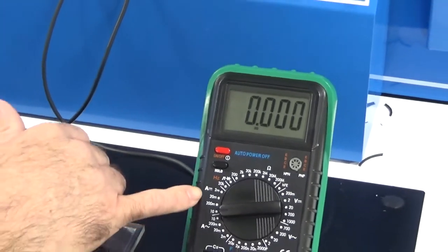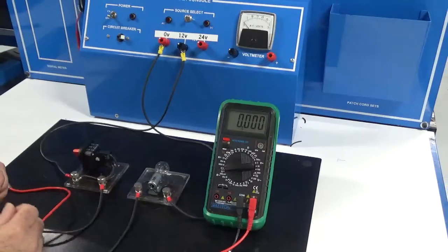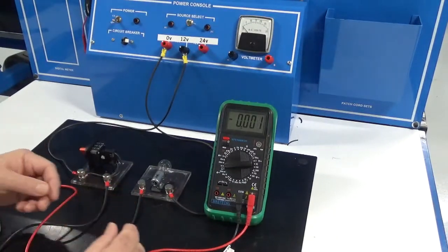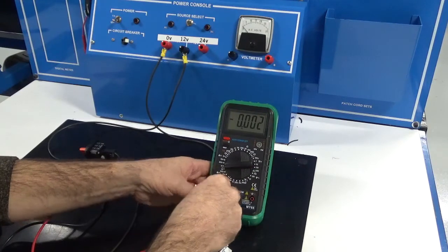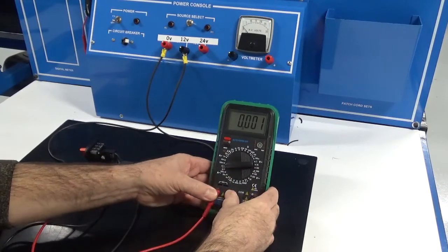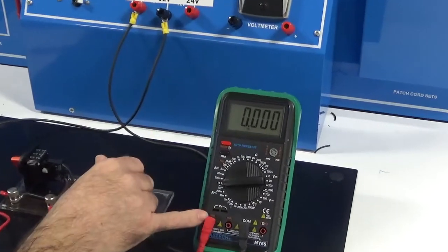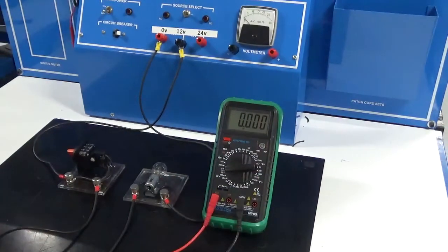If we try to measure that in the milliamp range, we could damage the meter or blow an internal fuse, and you have to go and replace the fuse and hopefully not hurt your meter. But since we know we're going to be above the 200 milliamp range, we're going to go ahead and set it up for the 10 amps. So I have to move my probe over here to the 10 amp jack on the meter, and to make a current read, the current actually has to be flowing through the meter.